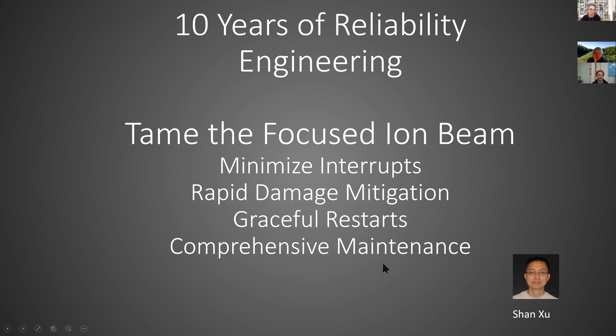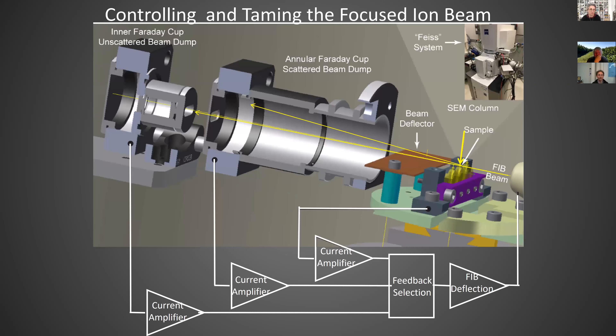We implemented a comprehensive maintenance plan, a special temperature-controlled room, and rapid warnings if something goes wrong. One key modification involves monitoring the focused ion beam: the FIB beam comes across the sample surface and can be dangerous if it cuts too low. We monitor the FIB current going over the top of the sample, the amount scattered from the surface, and the current going into the sample itself. We use a combination of these to determine how much to deflect the beam.